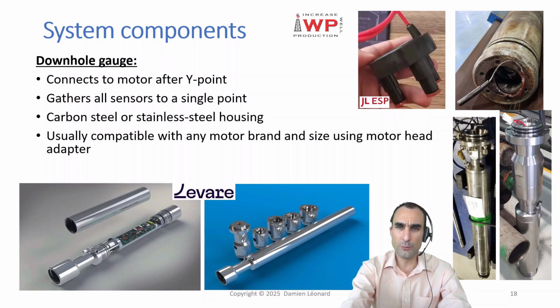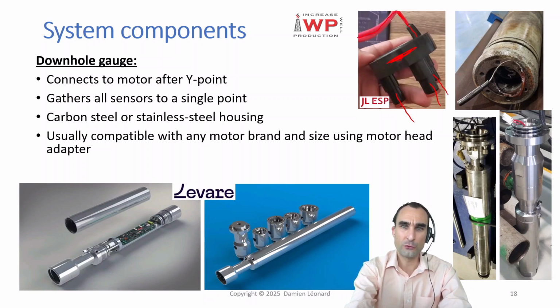So basically, at the bottom of the motor, the three phases of the motor will connect to each of these three pins over there, and they will connect together somewhere inside of this piece. And then you will still have this red cable that will be used to connect it to your ESP gauge so that the DC signal can be sent to your ESP gauge.